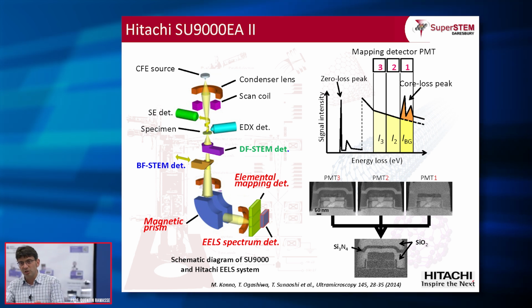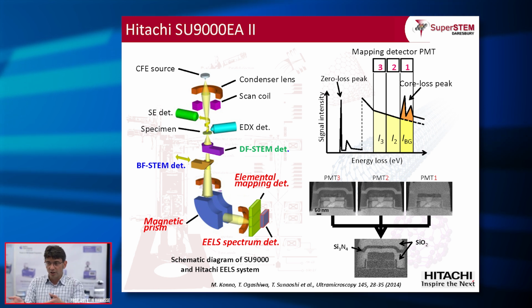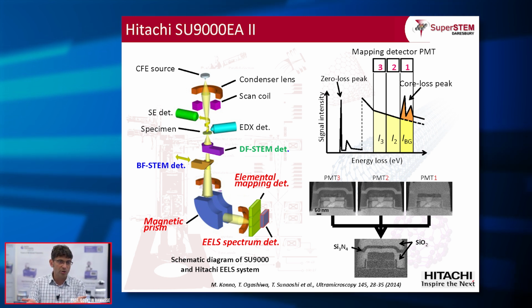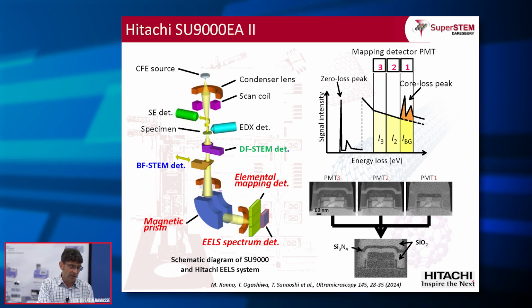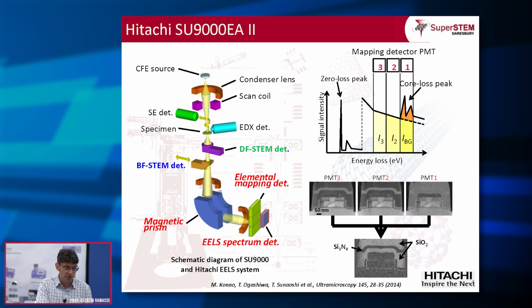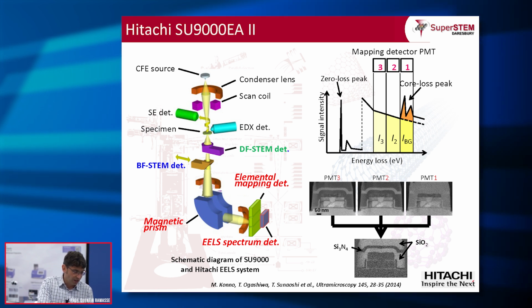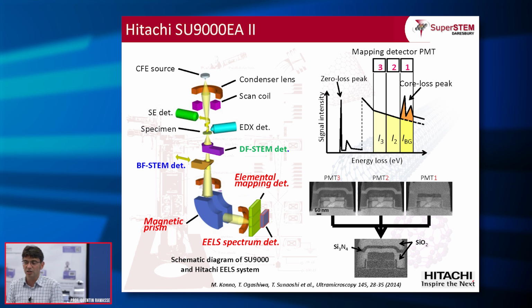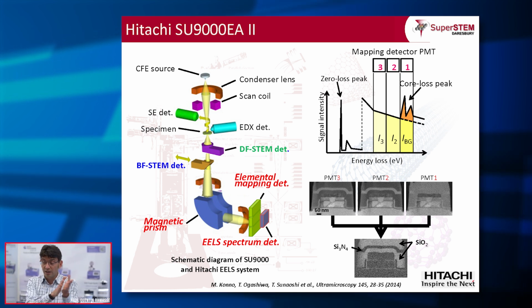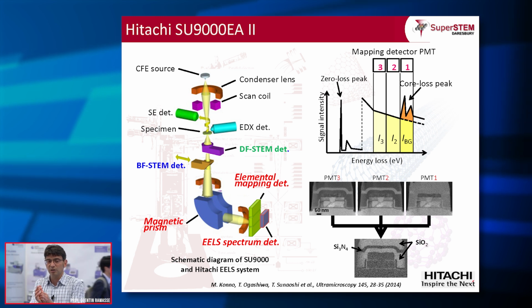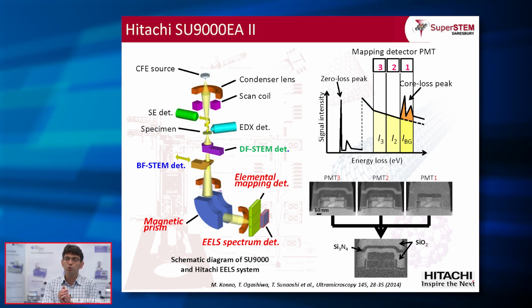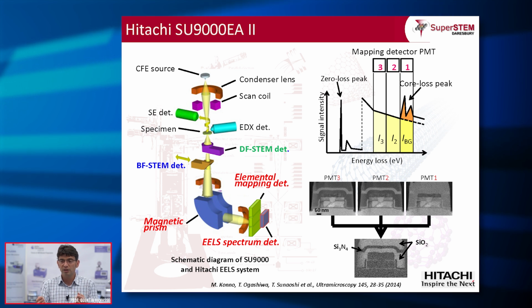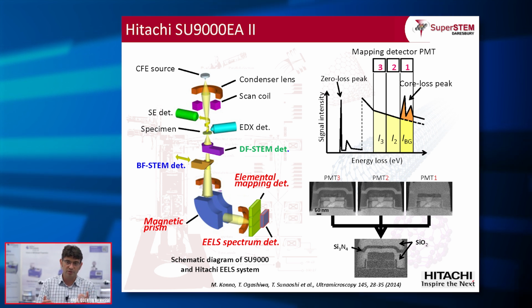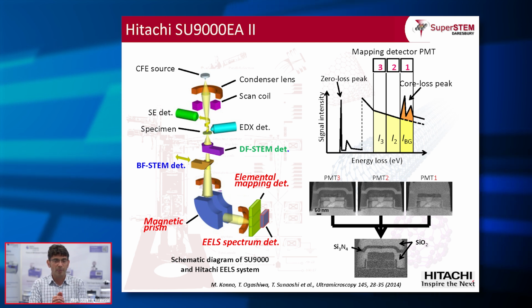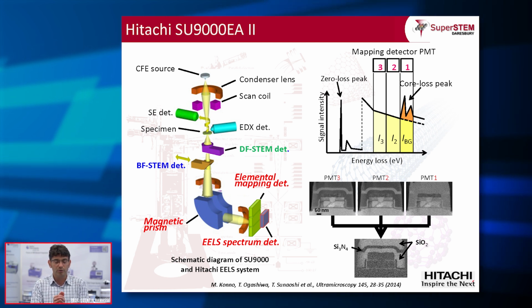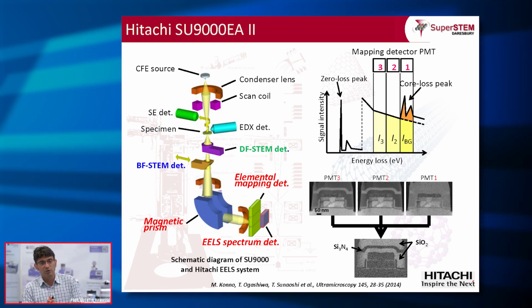As you would in any EELS spectrometer, you will have a CCD camera, so you just spread your beam into your rainbow illumination, and then you put this on your CCD, and you get your zero loss, your plasmon, and your core loss. But it also has this, what they call elemental mapping detector. Essentially, that was designed, as far as I know, and again, I'll defer to my colleagues, for the semiconductor industry, as a way to do very quick elemental mapping for low Z elements. So carbon, silicon, et cetera, nitrogen, when the new era EDS detectors were not available.